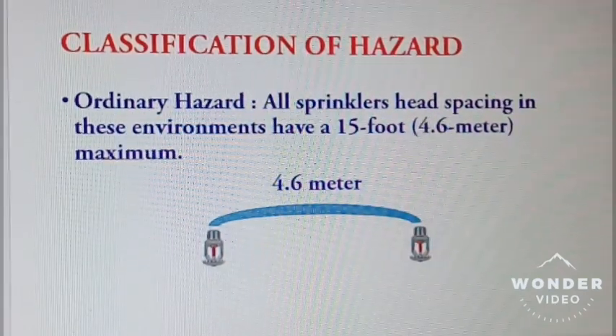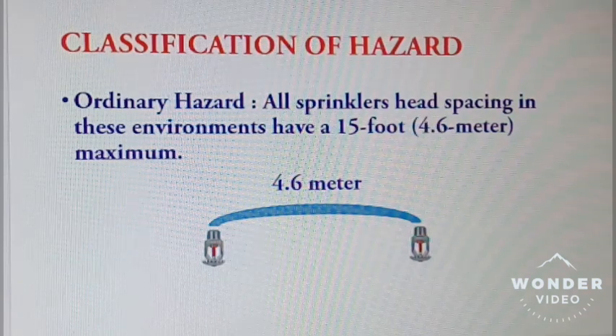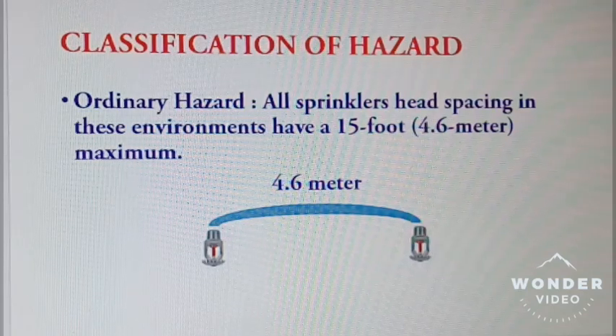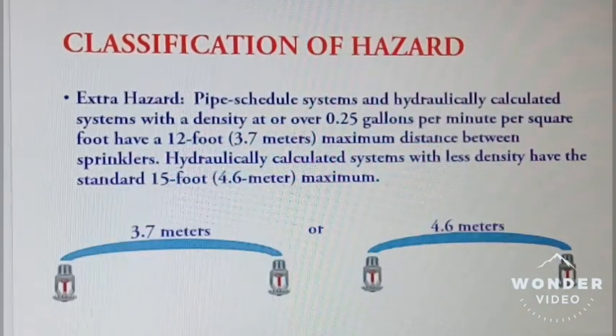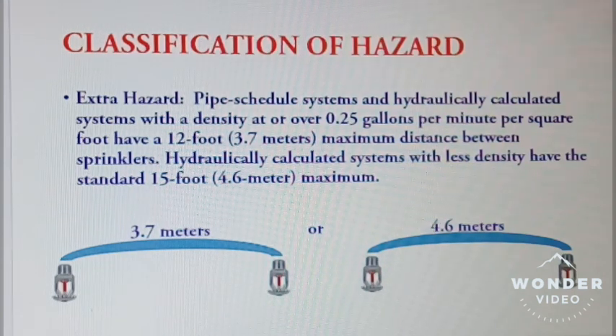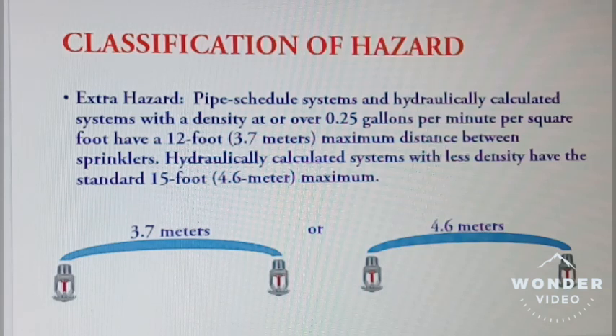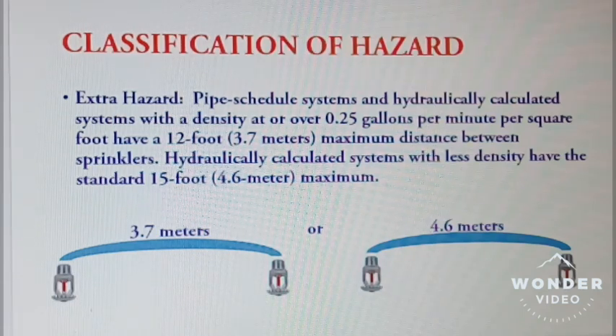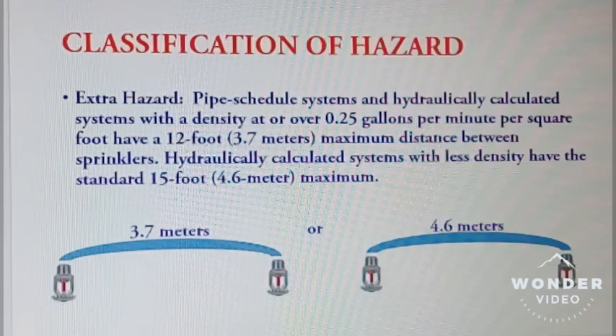Ordinary hazard: all sprinklers in this environment have a 15 feet, equivalent to 4.6 meters, of maximum spacing between them. Hydraulically calculated systems with less density also have the standard 15 feet, equivalent to 4.6 meters, of maximum spacing between them.